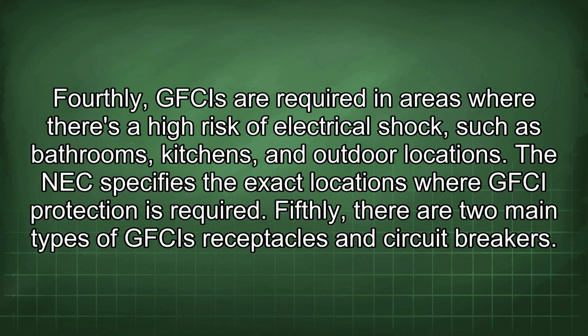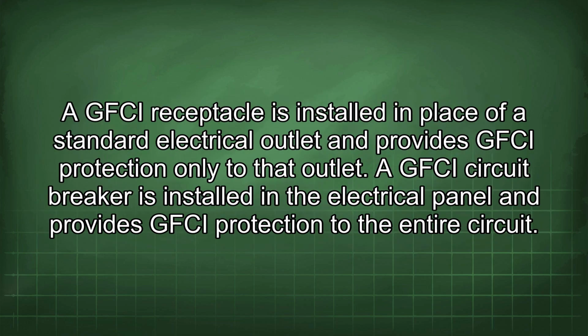Fifthly, there are two main types of GFCIs: receptacles and circuit breakers. A GFCI receptacle is installed in place of a standard electrical outlet and provides GFCI protection only to the outlet. A GFCI circuit breaker is installed in the electrical panel and provides GFCI protection to the entire circuit.